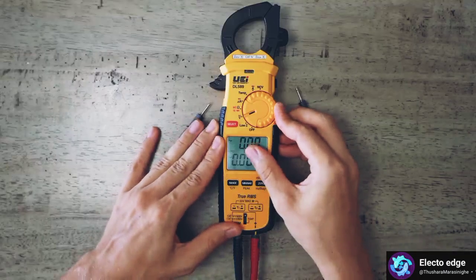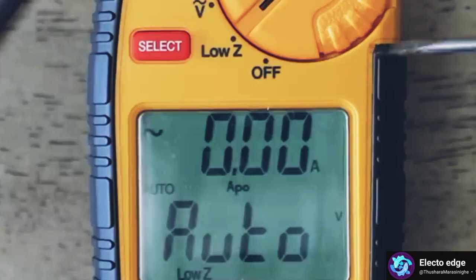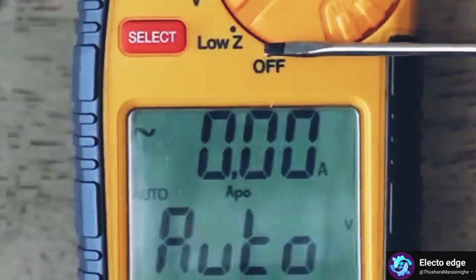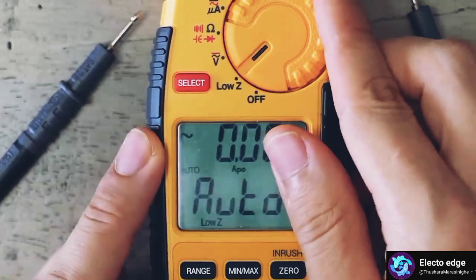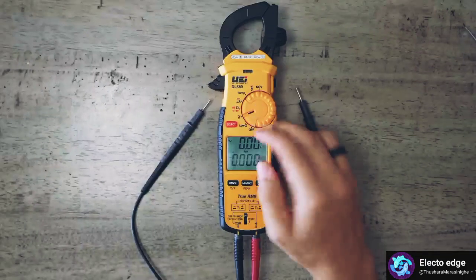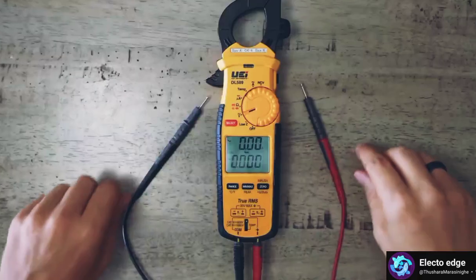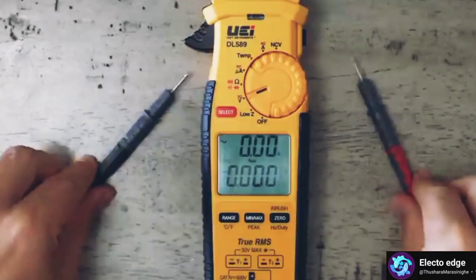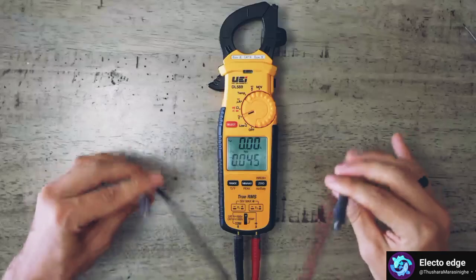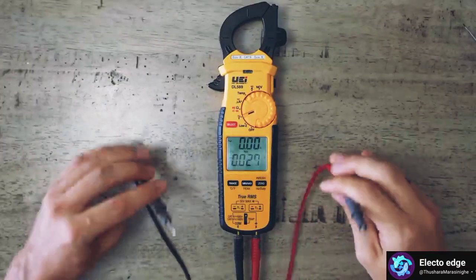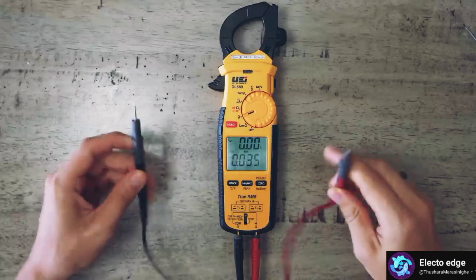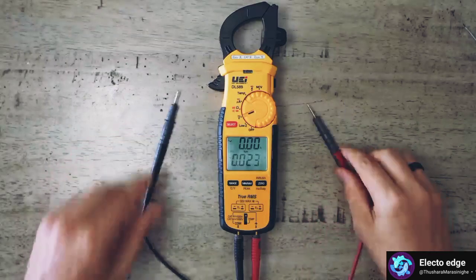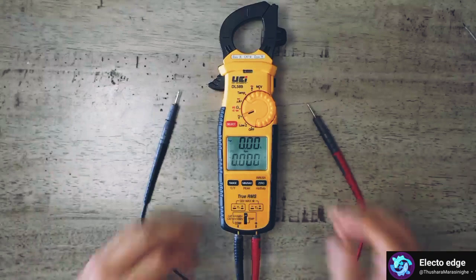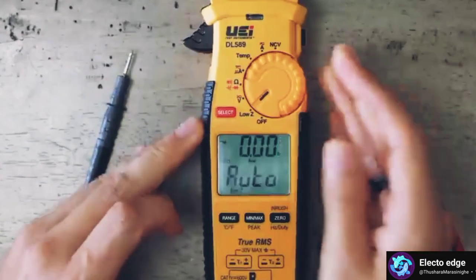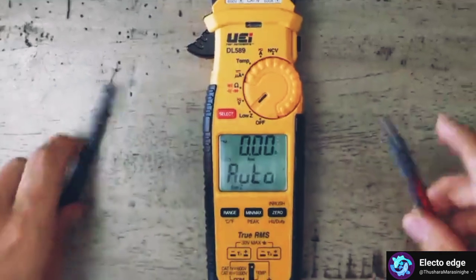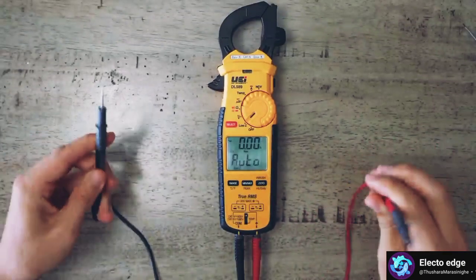Some meters will also have a low Z voltage setting. Low Z stands for low impedance and is used to eliminate ghost voltage. When I have my meter set to voltage, it is a lot more sensitive than the low Z setting. It catches any kind of fluctuations in voltage. For example, even if I start wiggling my leads, look at that. Even just wiggling my leads gives me a little bit of a ghost reading. So if you're checking an outlet or any kind of power wires, the ghost voltage could be a lot higher than that. But if I switch my meter to low Z, it becomes less sensitive to those fluctuations, and it's not going to pick up any kind of ghost voltage.